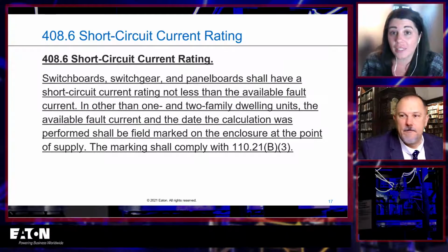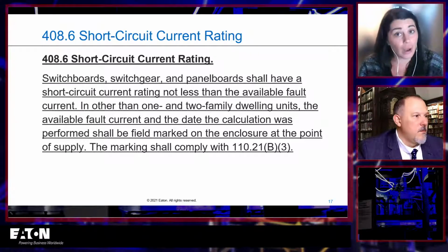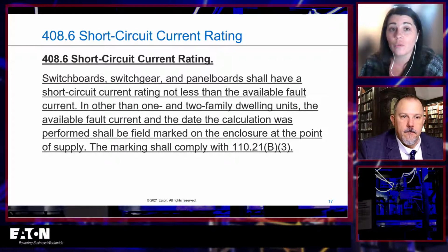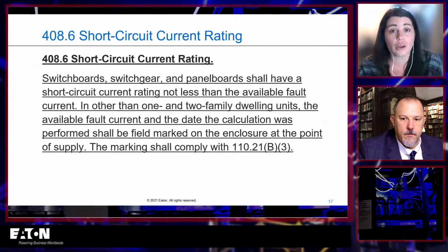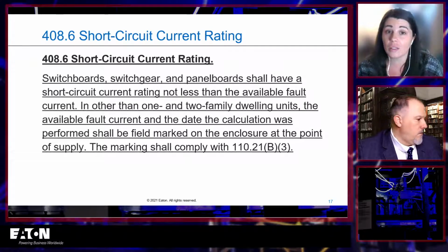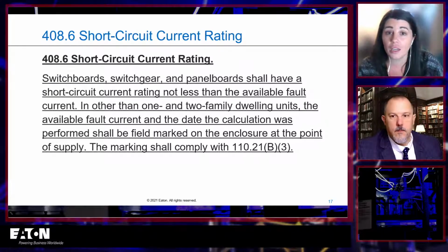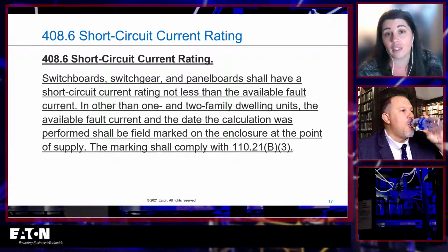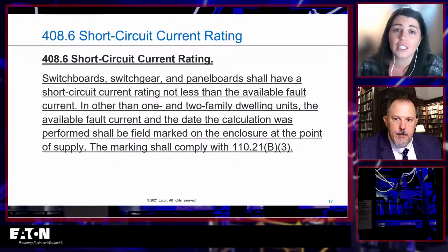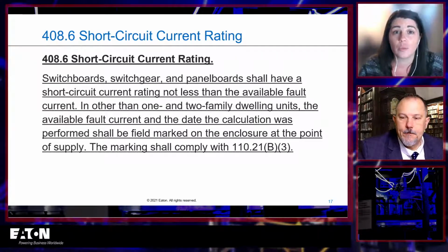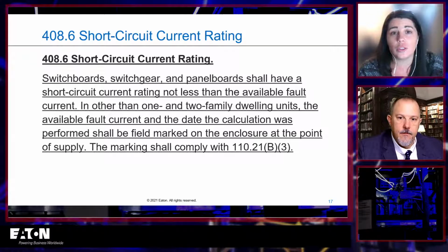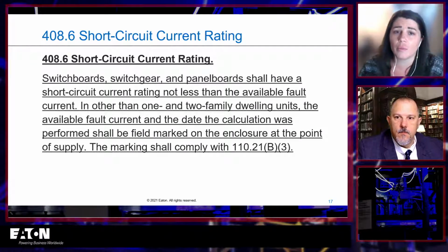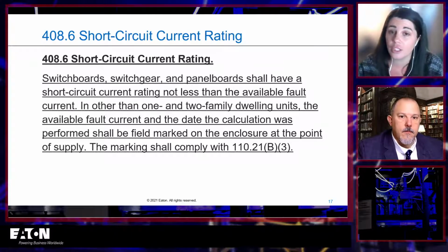So the next update, right? This was a 2020 update, Article 408, and that's for switchboards, switchgear, and panelboards. So now they also need to have a short circuit current rating not less than the available fault current, right? There are some exceptions in there. For one- and two-family dwelling units, you don't need to have that available fault current calculation done, but everything else should have it. So that's a new addition.